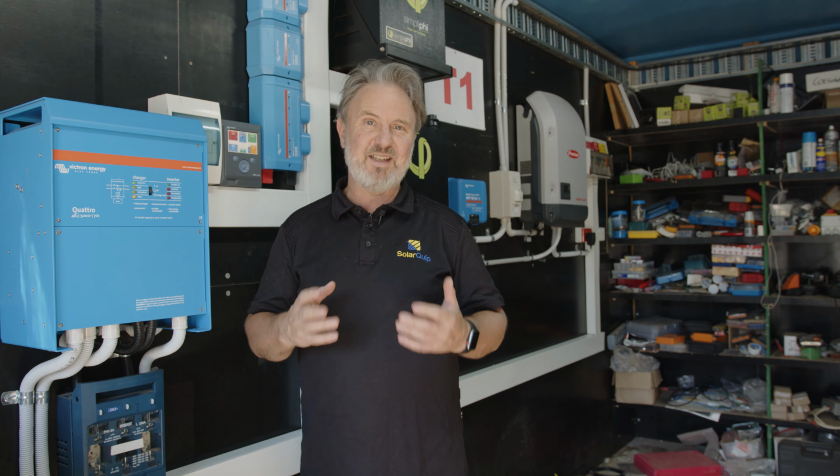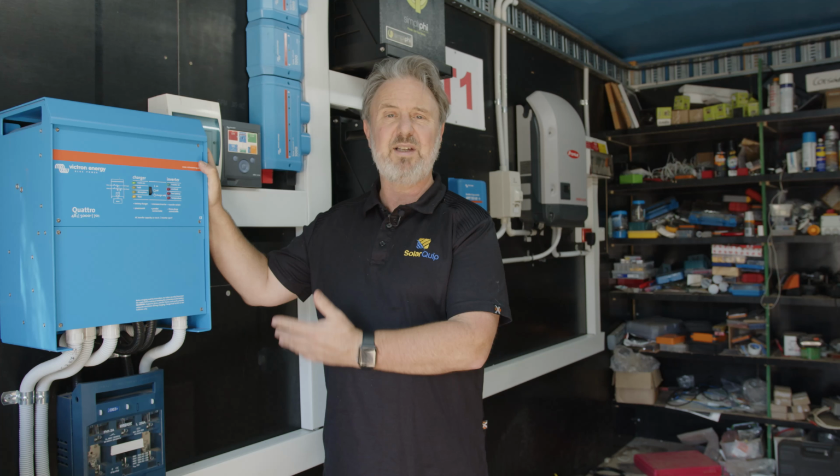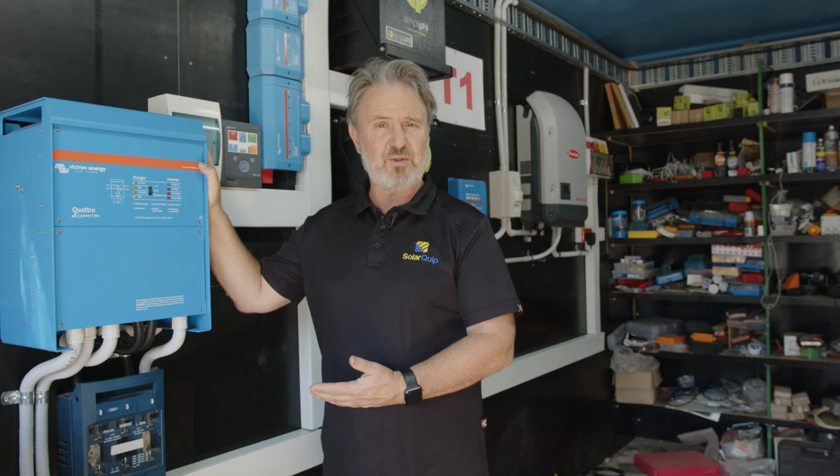Now, black start protection is for when all things go wrong, such as your backup generator fails to start. It's run out of fuel, you haven't done any maintenance in a while, and it cranks three times and doesn't auto start, it's broken down completely, it's not there. Any of those reasons and more could explain why your backup generator isn't going to come online and charge your batteries. So the Victron inverter, once the Quattros see a certain trigger point, will shut down to protect the battery system.